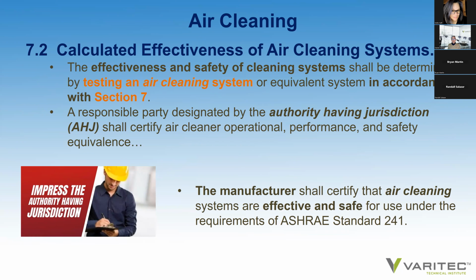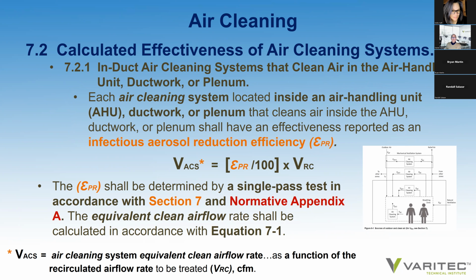The effectiveness and safety of cleaning systems shall be determined by testing an air cleaning system in accordance with section 7 of the standard. It also has language that says a responsible party designated by the authority having jurisdiction shall certify air cleaner operational performance and safety equivalence. So is that the local municipal authority who determines that during the startup and commissioning phase of a building? It also goes on to say that the manufacturer shall certify that air cleaning systems are effective and safe, appropriately applied in order to be used to meet the requirements under ASHRAE Standard 241. While there is calculated effectiveness for different types of air cleaning solutions, there are in-duct air cleaning systems that clean air in air handling units.